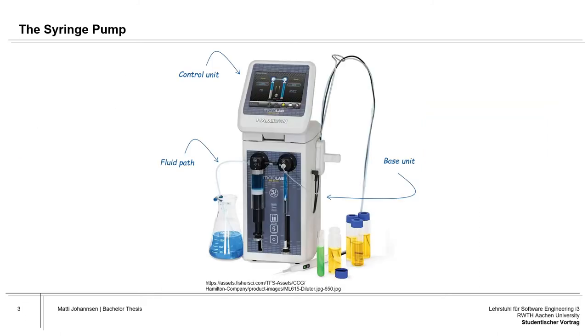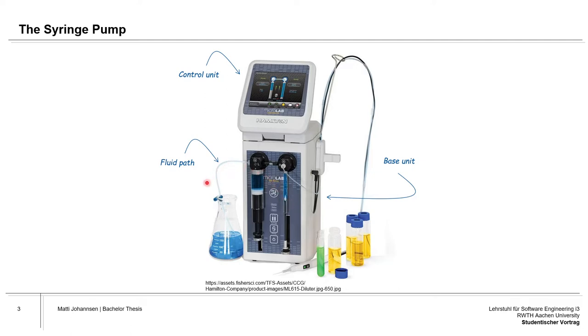For the synthesizing of these nanobodies, a syringe pump is used which consists of three parts. First of all, we have the base unit which is controlling the hardware workflow. Then we have the fluid path which ensures the sterility of the system. And then we have the control unit which is connected with an Ethernet cable to the base unit and with which the user can control it.